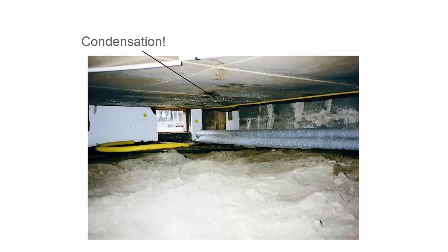But during the summer and early fall it's quite cold inside the crawl spaces, since you have contact with cold soil, and the outdoor air is filled with moisture. During the summer we have as much moisture as possible in the outdoor air. It comes into the crawl space by ventilation, and the relative humidity increases, and sometimes we get condensation, as in this picture.